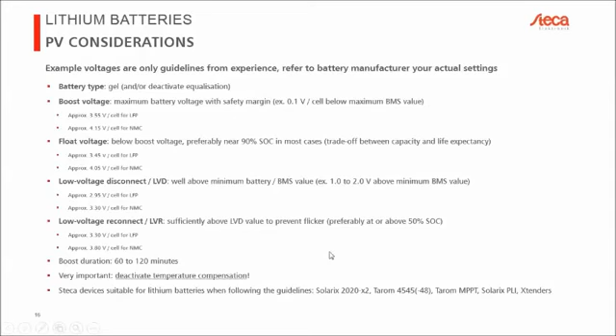There are two exceptions. One is the Xtender, which is particularly well suited because it can really communicate with the battery, so you can even use battery types that require communication. The 6000M is also particularly suitable for lithium because even though it doesn't communicate with the battery, it gives you much more control over the charging parameters.